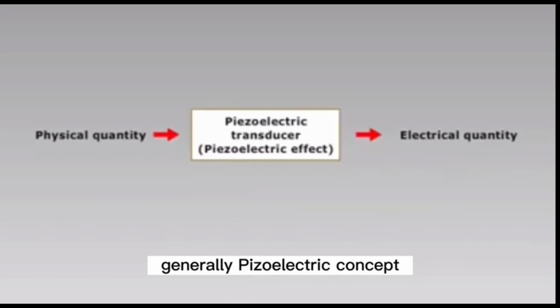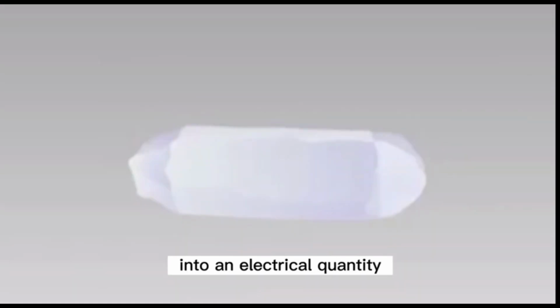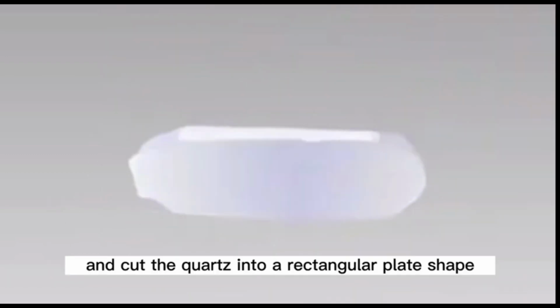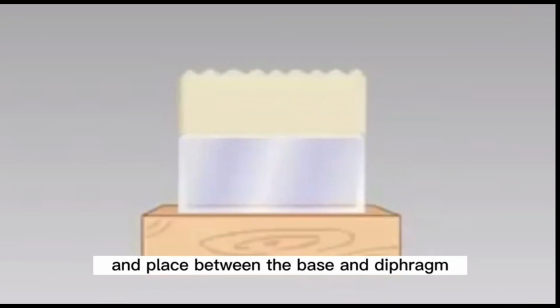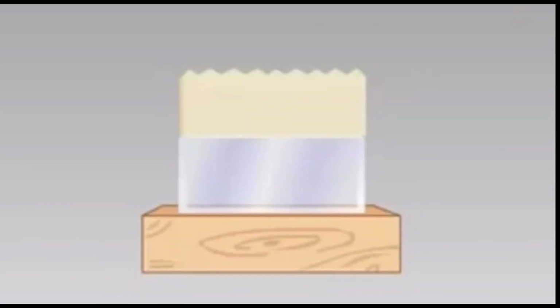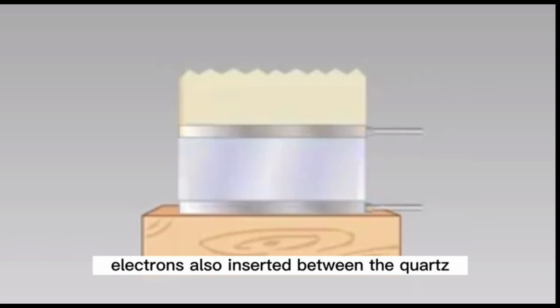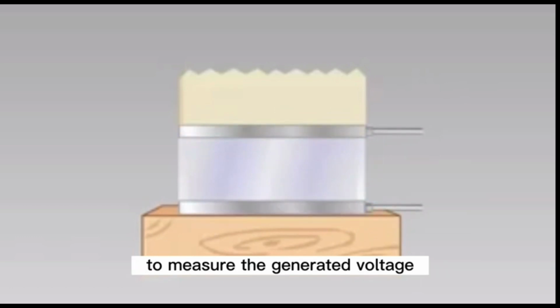Generally, the piezoelectric concept is to convert a physical quantity into an electrical quantity. Due to its high stability in nature, we use quartz, cutting it into a rectangular plate shape and placing it between the base and diaphragm. Electrodes are also inserted between the quartz to measure the generated voltage.